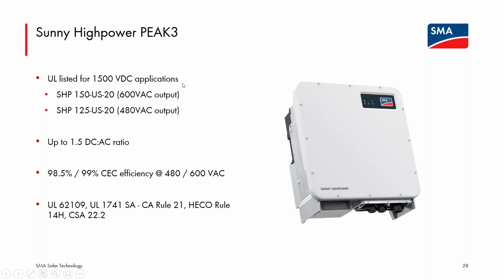So there are 2 variants of the PEAK3 that have UL listing. One is a 125 kilowatt unit that outputs natively at 480 volts 3-phase. The 150 kilowatt model outputs at 600 volts 3-phase. So the power class locks in the AC service that the inverter ties to. So those 2 power classes, 125 kilowatt or 150 kilowatt, again, you have a single positive and negative DC input coming to the inverter.